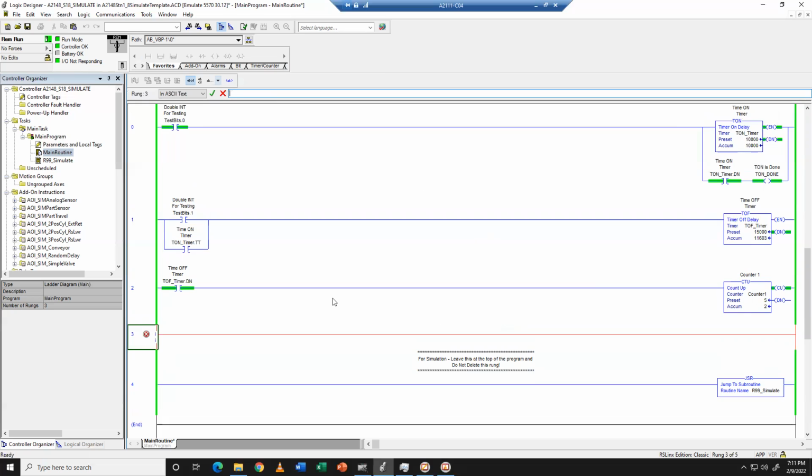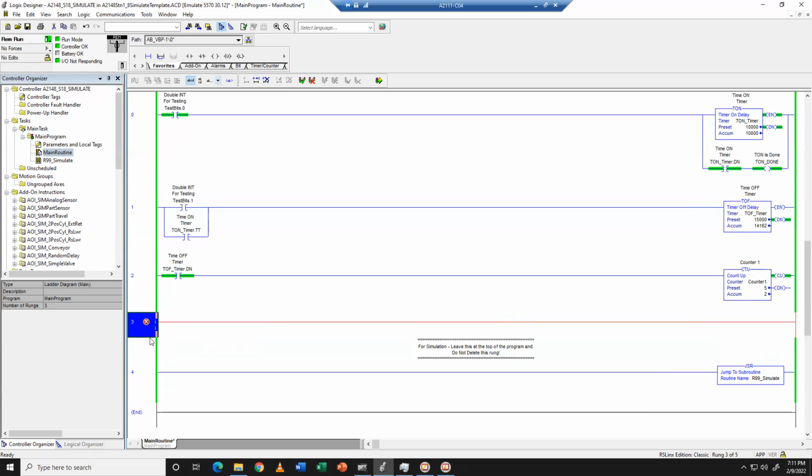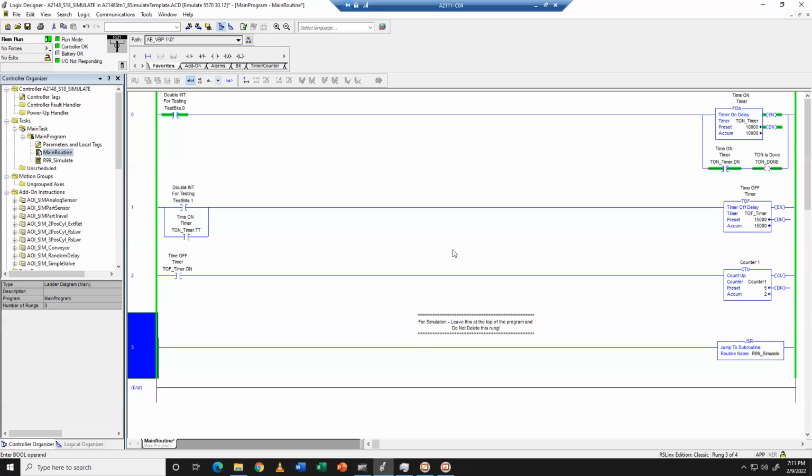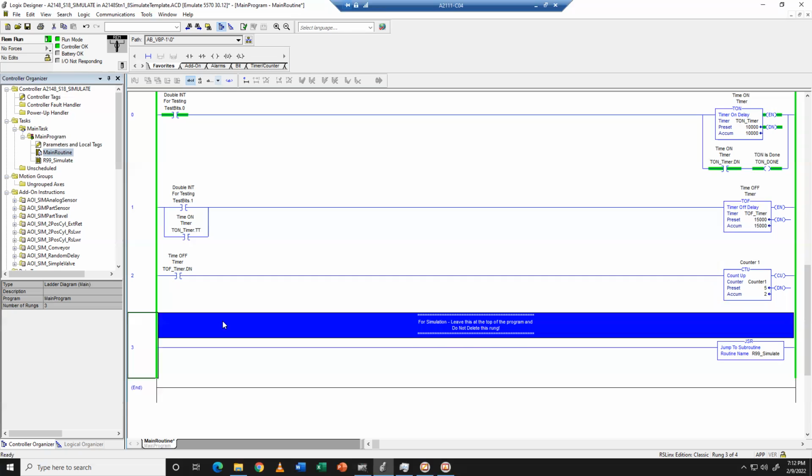So you can have lots of counters. I've seen counters used to do math, for volume calculation, knowing that one input turning on becomes a pulse for a tipping bucket gauge. You count the number of tips, and then you can perform math on these accumulators.